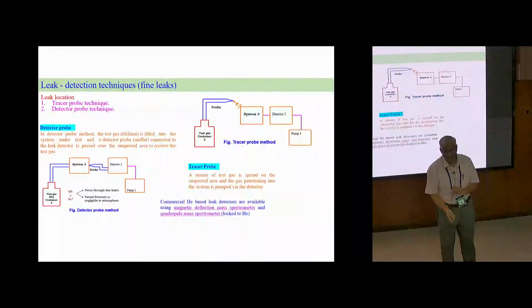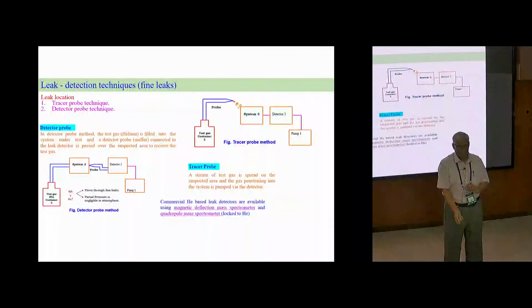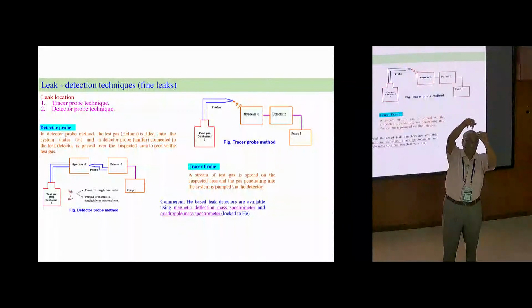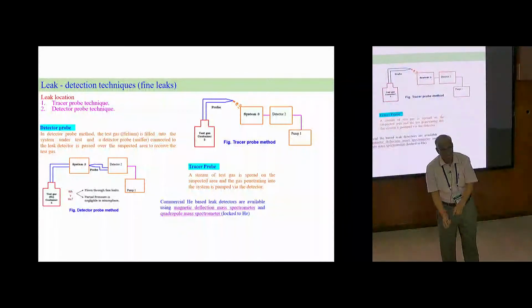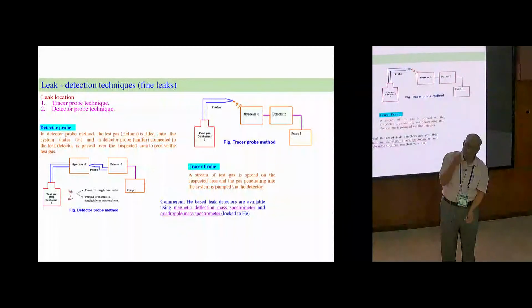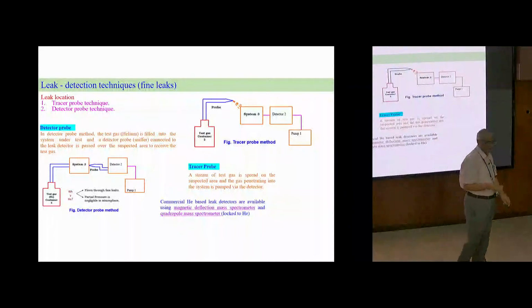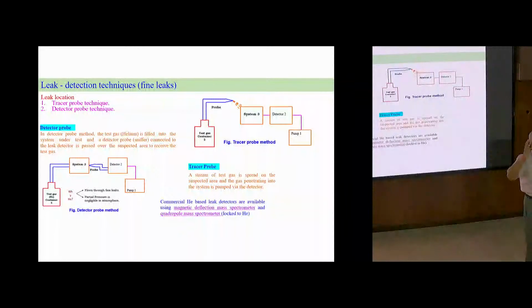You have to start leak checking from the top, not the bottom. If you check from the bottom, the gas will rise upward, and you'll think there is a leak up there and try to solve it, creating trouble. So always leak check from top to bottom, never bottom to top, because light gas like helium will rise and go through. You'll get a false signal, an alarm, and you'll stop everything for days chasing a leak that doesn't exist.